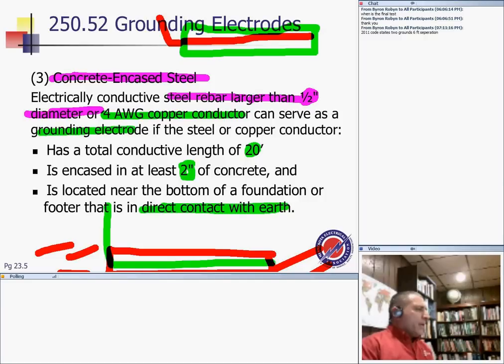And guys, about concrete encased electrodes. Concrete encased steel or electrodes are one of the best electrodes that you can get, guys. If you have concrete foundations with all this rebar, you tie them together. In 2011, they allow you that 20 feet to be segmented. So here's 10 feet, and here's another 10 feet, and these are tied together rebar. So they don't have to be one continuous 20-foot section. It could be different sections tied together with approved methods for the rebars. Exothermic or actually rebar ties are also approved. So this is one of the best ones that gets you a low impedance to ground.